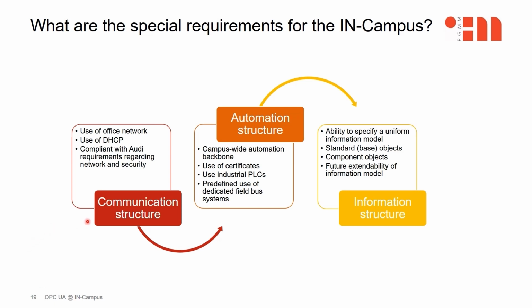Let us first take a look at the communication structure. From the very beginning, there was a desire to use a single communication structure on the INCampus. This meant that it was clear that the office network operated by Audi IT was to be used. Hence, network management for all components connected to the office network is the responsibility of Audi IT. This also means that static IP addresses are not permitted for the programmable controllers. Instead, the dynamic assignment of IP addresses is carried out automatically by Audi IT on the basis of the DHCP protocol. The security specifications of Audi IT must be complied with.